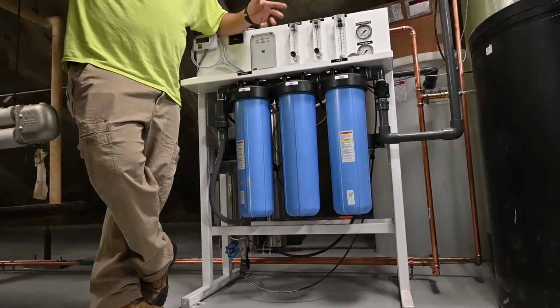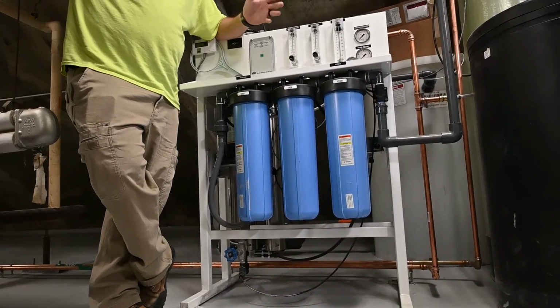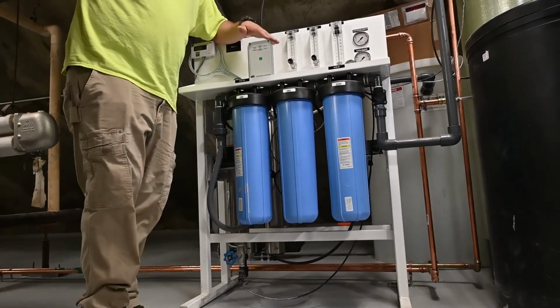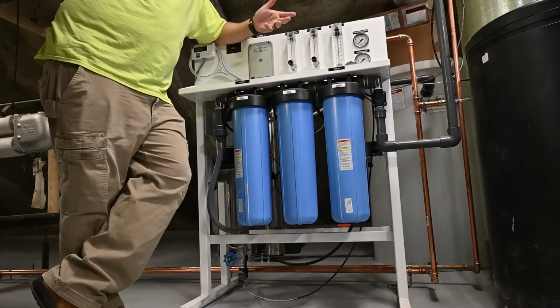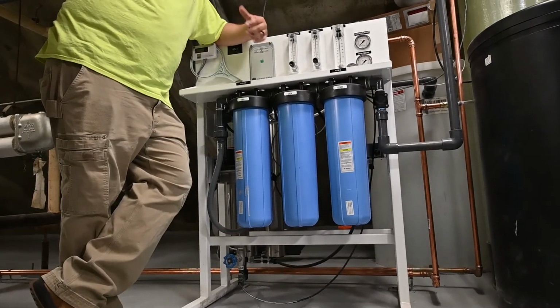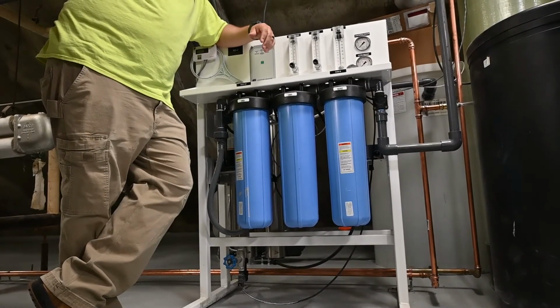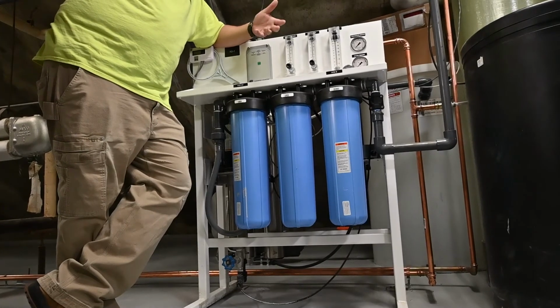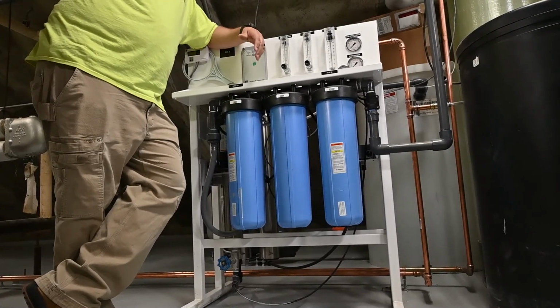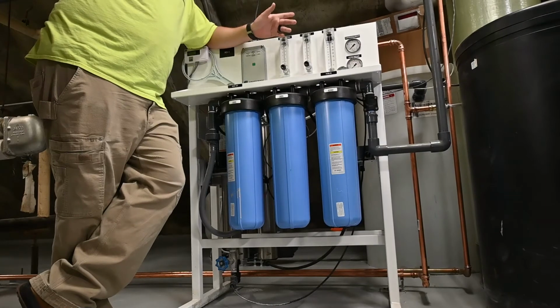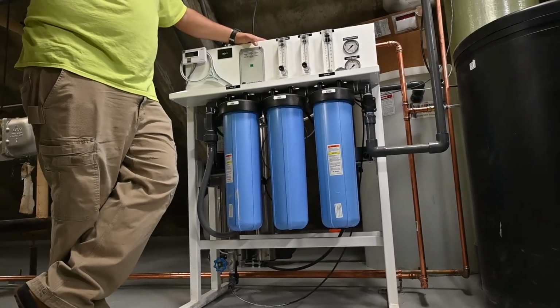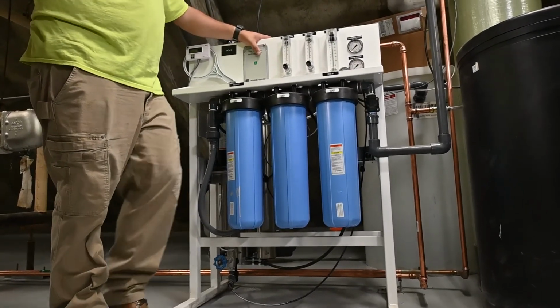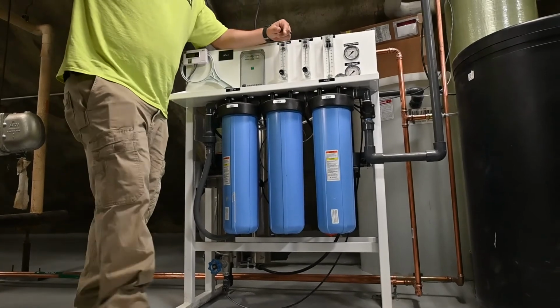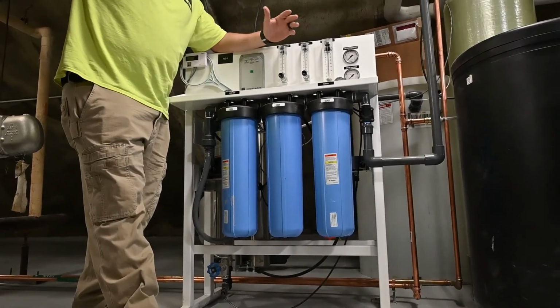Adding salt inside the tank: right now, it's about 30%, 40% full on salt from the bottom of the tank. That's a good place to keep the salt level. You want to make sure there's always salt in this tank right here so that we're able to adequately create the RO water that we need. Behind it is the filling tank. You can see right here it says tank full. This LED will light up when it's full. There's a float inside there that's going to come back to the system to tell it that it's full.